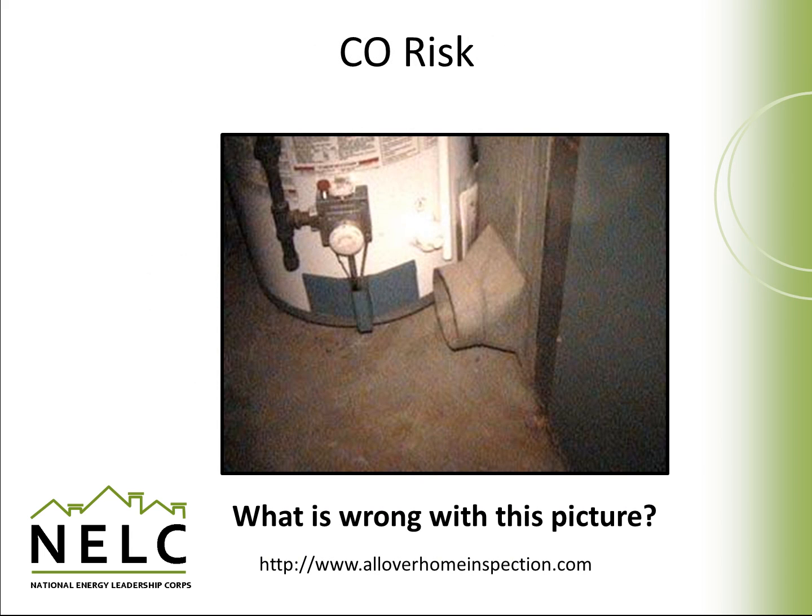This is a picture of a gas water heater installed next to a gas furnace. The opening in the furnace ductwork in the center of the picture is sucking in a large volume of air into the furnace when the furnace fan is running. The problem is that the air being sucked into the furnace at this duct can be sucking in all the carbon monoxide that's being released from the combustion in the water heater and distributing it throughout the house.